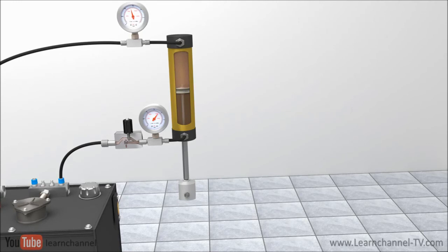But be careful. If you close the flow control valve too much, the pressure at the outlet port of the cylinder can rise even to a value above the pressure you get from your hydraulic power pack.